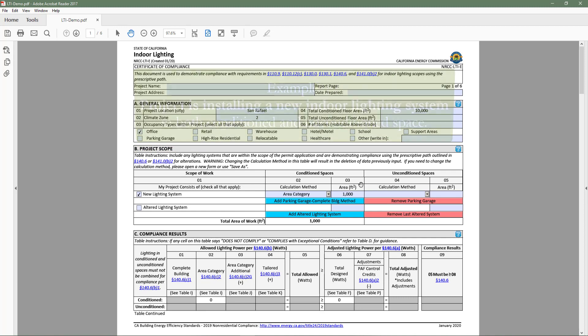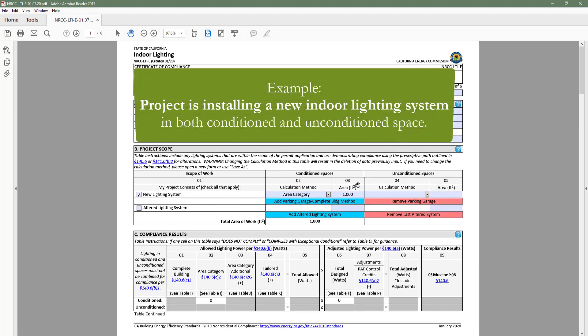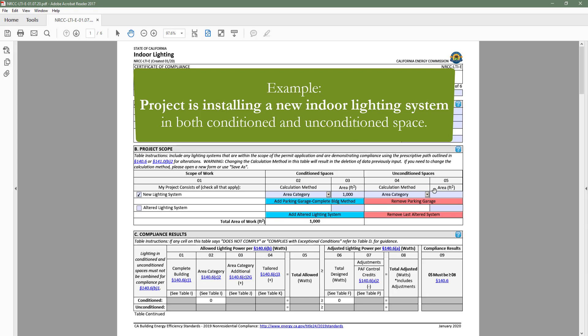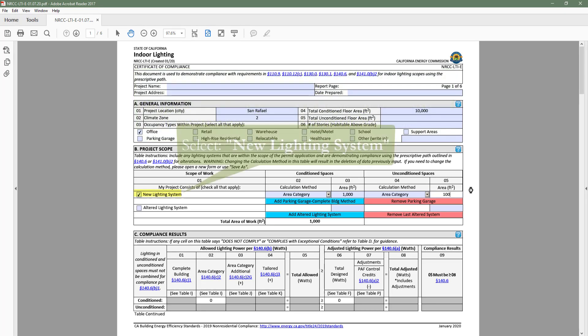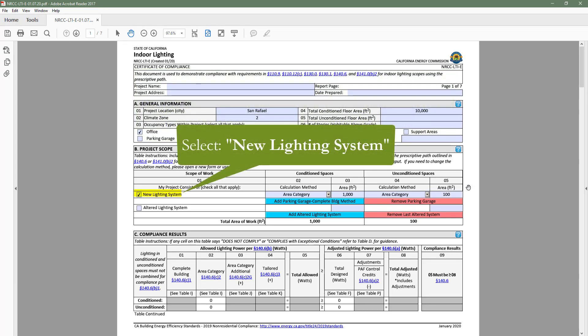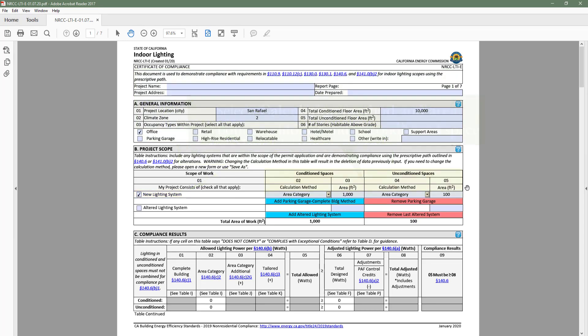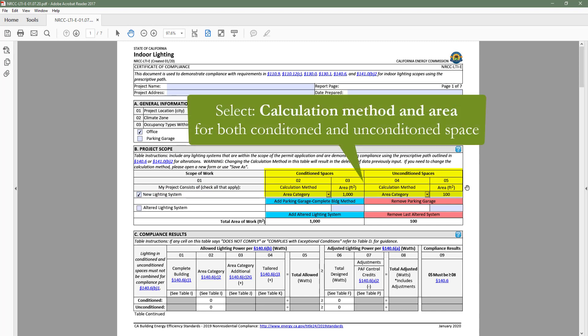For example, if our project is installing a new indoor lighting system in both conditioned and unconditioned space, we would select new lighting system in table B, as well as input our calculation method and square footage for both conditioned and unconditioned space.